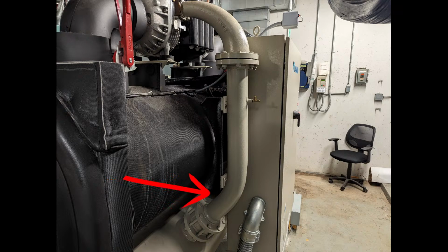So this whole process, it doesn't have too much of the pressure being relieved off of here, because we still need lift to be created to get the compressor spun up properly. So once we get up to speed, then we can close the part load valve, and the check valve will go into a full open state, and everything just runs normally from there. Like, that's just a real high level of what is happening with that process.